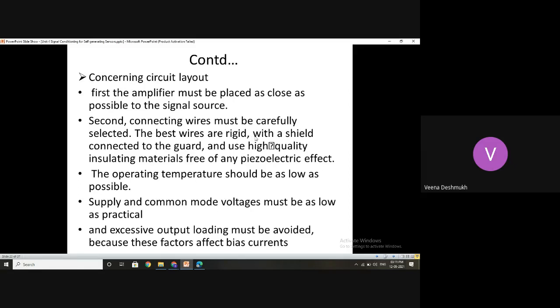So the best wires are rigid, with a shield connected to the guard, meaning all of them should be shielded. These shielded wires have to be connected to the reference potential. Connected to the guard means the guard is again connected to some reference point—it could even be zero potential ground. So they have to be properly shielded and guarded.